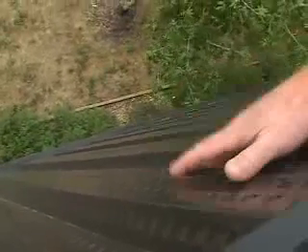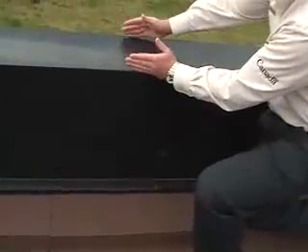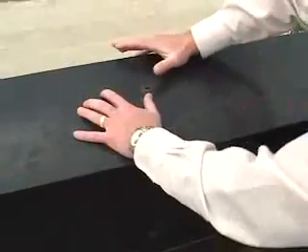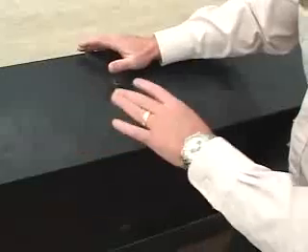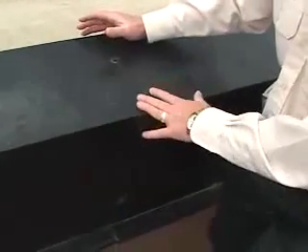What we have here is basically a perforated sheet metal wall, and we painted it a very dark brown, black type of color. And what you see here is the actual void. So the void you're looking at is probably about 6 to 8 inches, and it's simply air comes in, we heat it up through natural convection that occurs, and we move it through our air handling units and into the building. The amount of heating required depends on the outside ambient temperature.